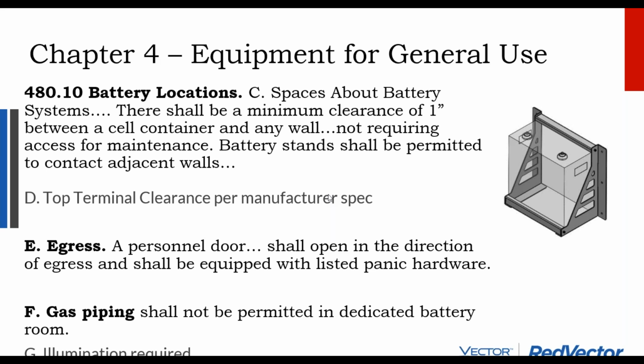And where that comes into play is, I did a project where we put the batteries outside the building, but the home was on a hillside, and we had a little alcove that we could put the batteries into, tucking them up against the building foundation in their own little dedicated space. Well, that little dedicated space, if it's not just a box that you're standing outside of and then working into, if it's an actual battery room, that battery room needs lighting. So if you're building a battery room adjacent to the building, it can't just be four walls and a ceiling. It needs to be a little bit more professional.